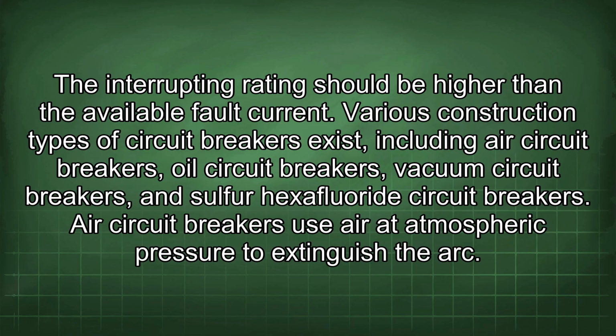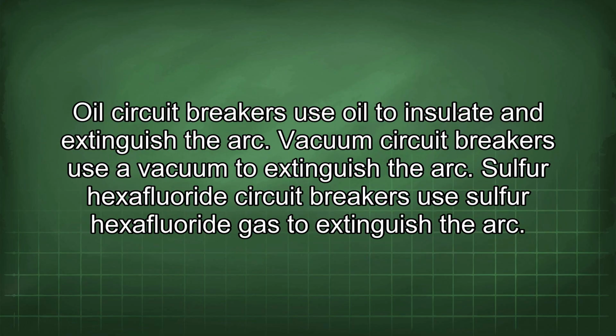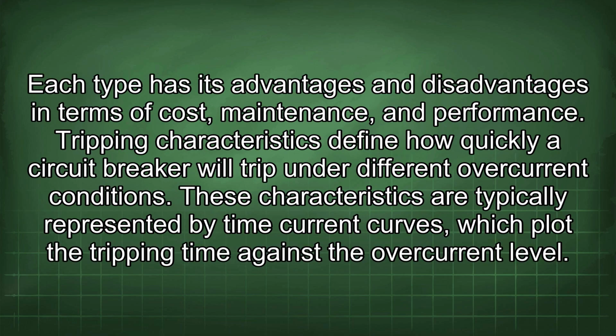Various construction types of circuit breakers exist, including air circuit breakers, oil circuit breakers, vacuum circuit breakers, and sulfur hexafluoride circuit breakers. Air circuit breakers use air at atmospheric pressure to extinguish the arc. Oil circuit breakers use oil to insulate and extinguish the arc. Vacuum circuit breakers use a vacuum to extinguish the arc. Sulfur hexafluoride circuit breakers use sulfur hexafluoride gas to extinguish the arc. Each type has its advantages and disadvantages in terms of cost, maintenance, and performance.